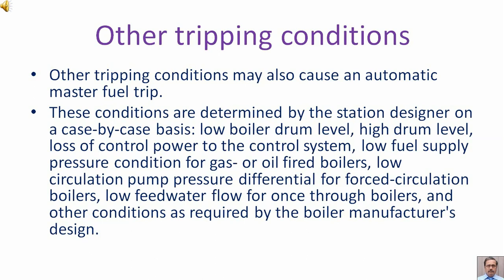Other tripping conditions may also cause an automatic master fuel trip. These conditions are determined by the station designer on a case-by-case basis. Low boiler drum level, high drum level, loss of control power to the control system, low fuel supply pressure condition for gas or oil-fired boilers, low circulation pump pressure differential for forced circulation boilers, low feed water flow for once-through boilers, and other conditions as required by the boiler manufacturer's design.